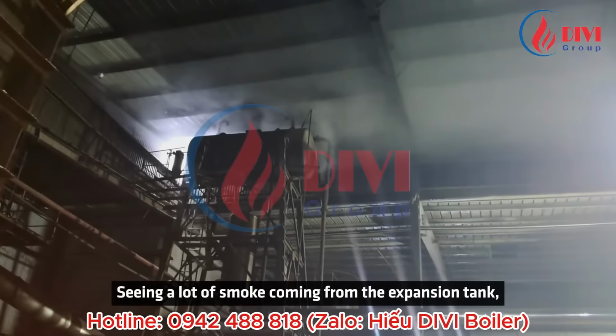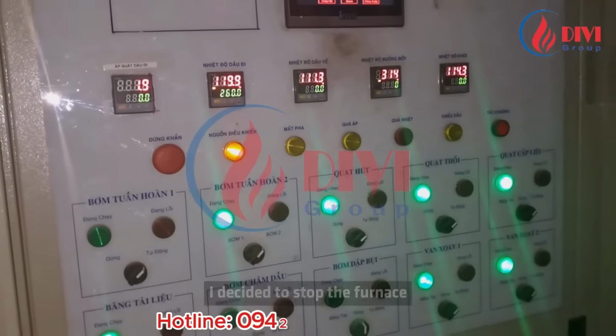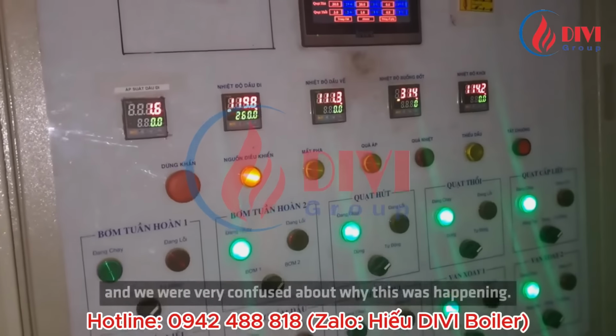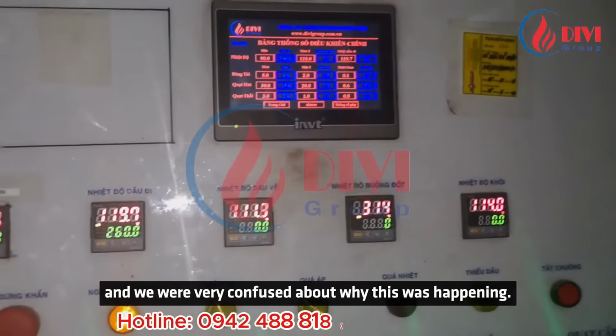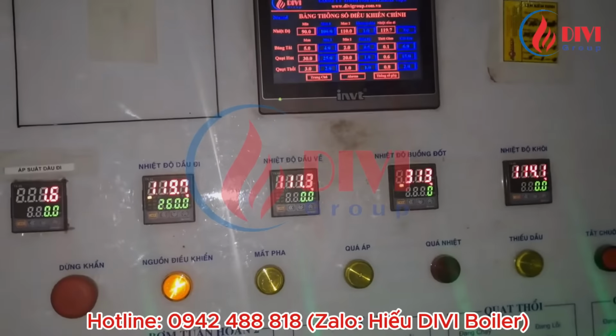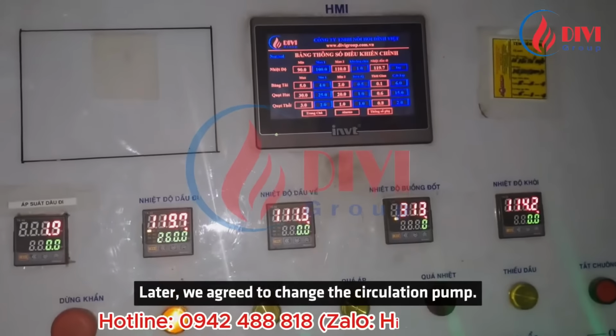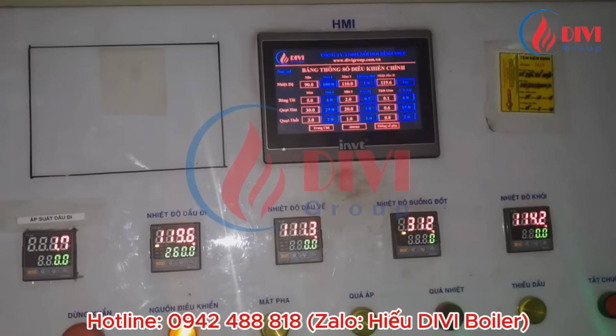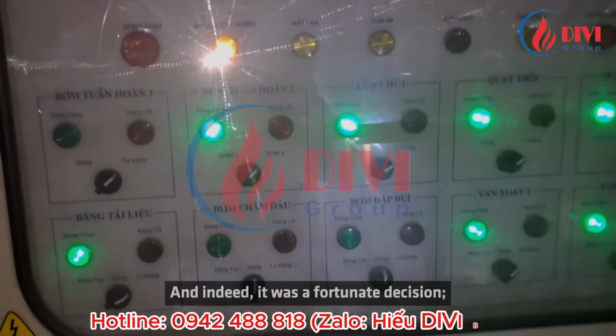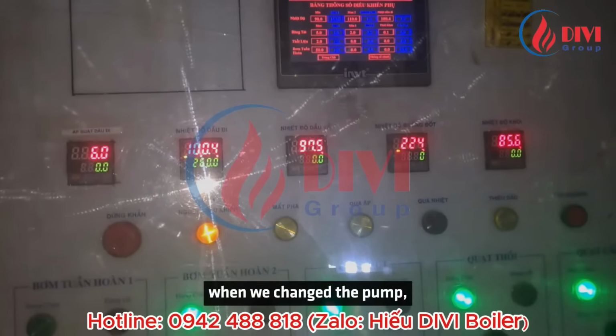Seeing a lot of smoke coming from the expansion tank, I decided to stop the furnace, and we were very confused about why this was happening. Later, we agreed to change the circulation pump. And indeed, it was a fortunate decision. When we changed the pump, all parameters and pressure returned to normal.